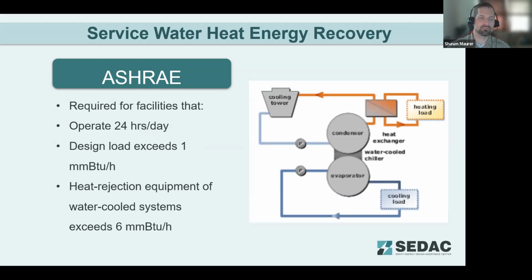For service water heating, ASHRAE is looking at recovering condenser heat for service water heating from HVAC chiller systems. Service water heating energy recovery is not required too often, as that 1 million BTU per hour water heating is a lot of service hot water. It's going to be a pretty big building. Additionally, there's that requirement that the facility operate 24 hours per day. So this is probably going to apply to more like hospitals, larger facilities with 24-hour occupancy. It's a pretty limited application.